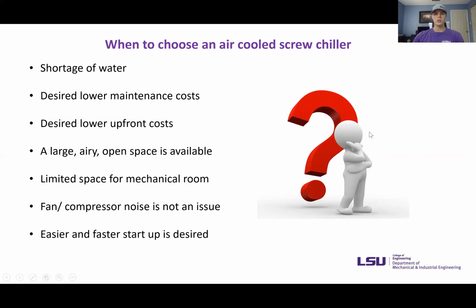So when would you want to choose air-cooled screw chillers? You'd want to choose an air-cooled screw chiller if there's a shortage of water, maybe if you live somewhere with a drought or with water restrictions like in California. If you desire a low maintenance cost because there are fewer parts on it, it's easier to work on. Lower upfront cost because essentially you have less equipment to install. You'd also want to use one if you have a large open area that's already available, or you can just put it on the top of a building to make things simpler.